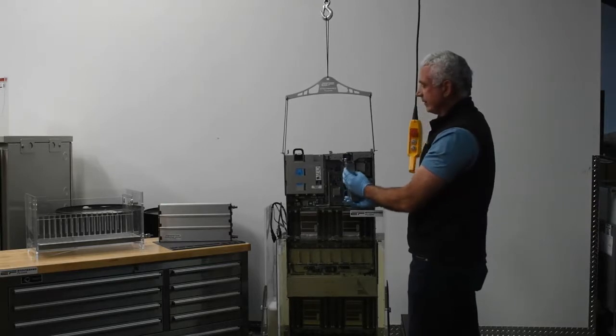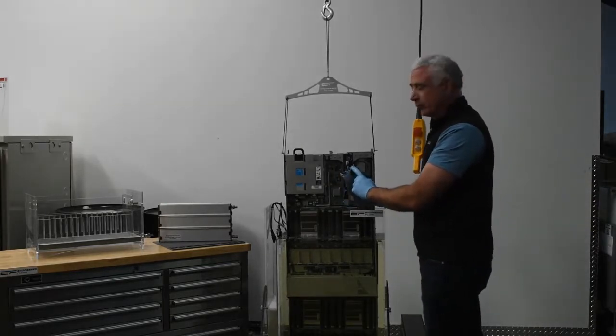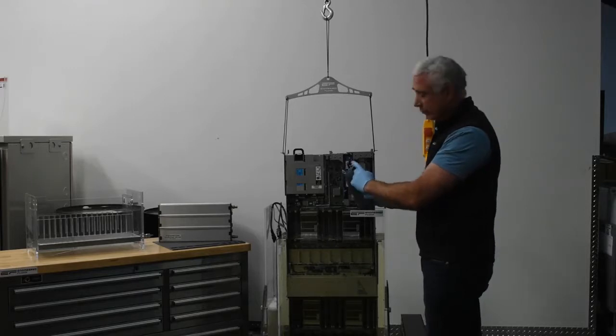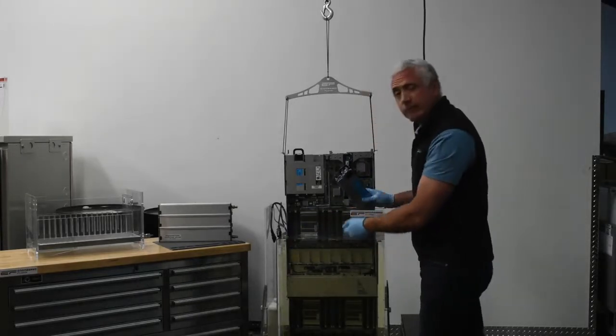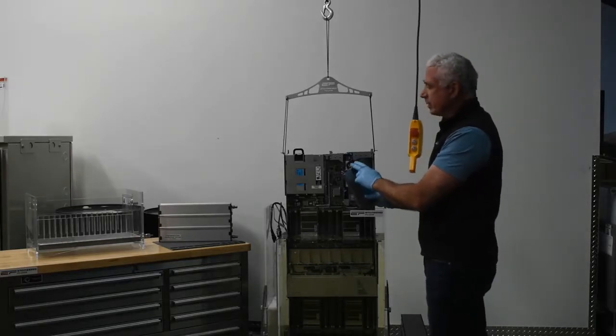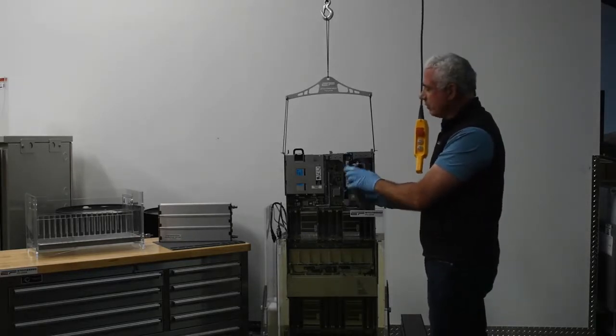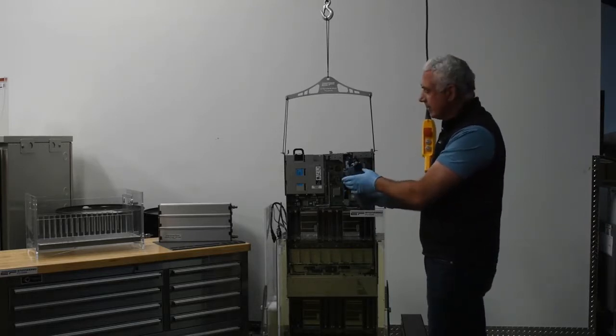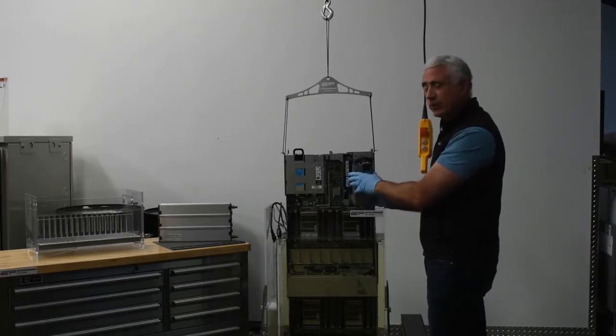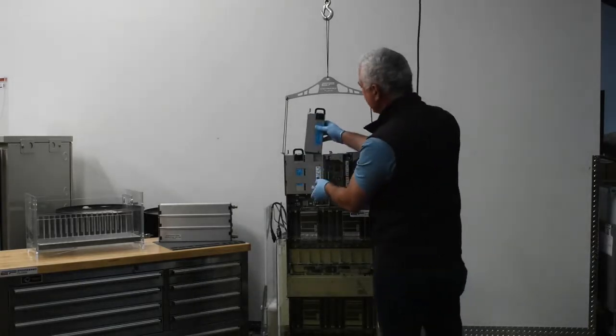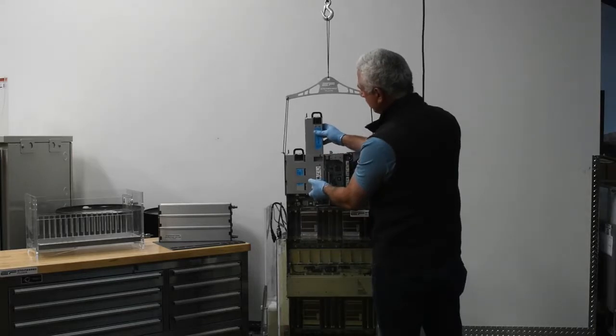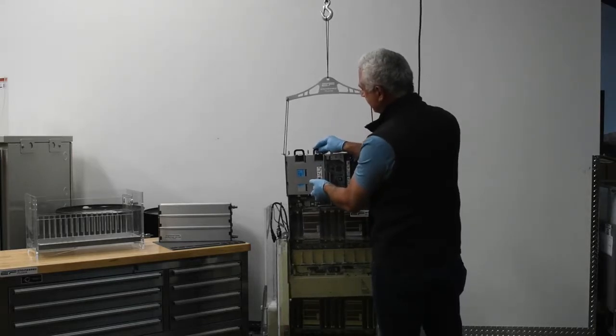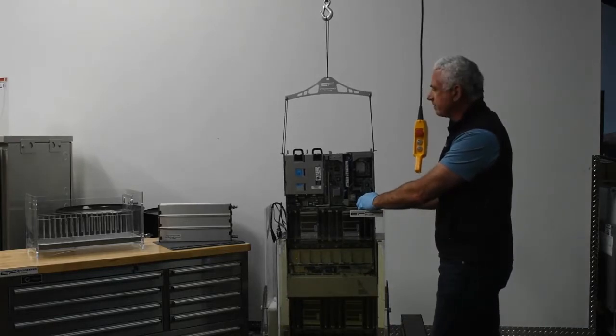One of the questions we often get is what about the fan on the power supply? Well in this case we've not removed these fans. We have removed the fans on the server itself but we've not removed the fan on these power supplies. For this particular brand of HP server if I were to remove this the power supply would shut down. In this case the fans will operate in the fluid, they'll operate indefinitely and there's no issue with that. So in this case if I've done my maintenance check or replacement I would simply reconnect this and get some nice positive locking as I push it back down.